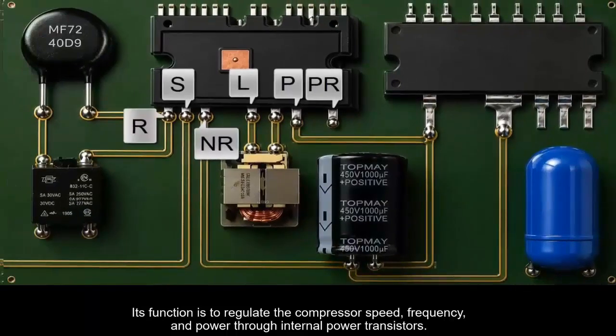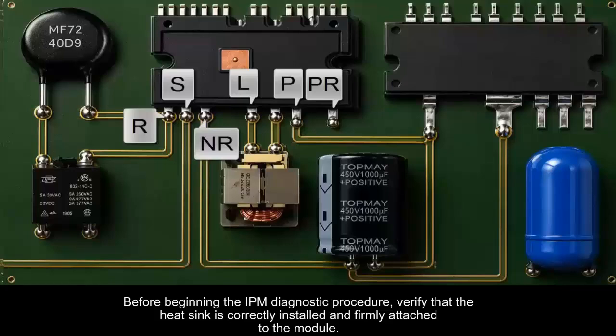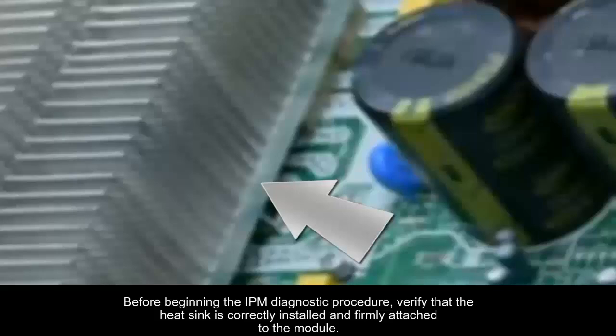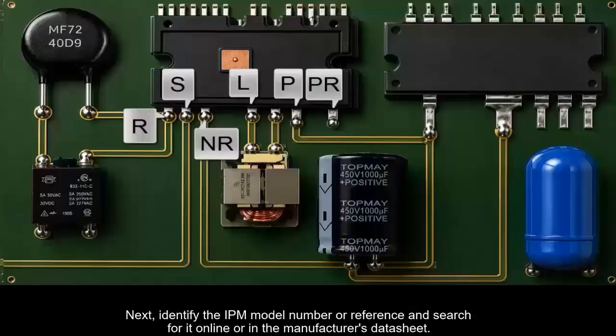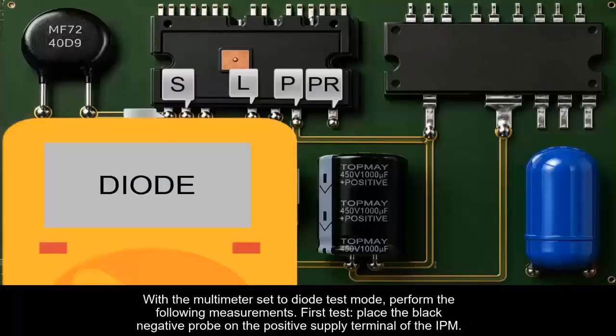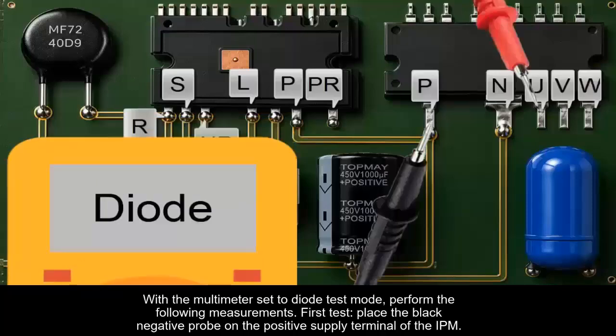Before beginning the IPM diagnostic procedure, verify that the heatsink is correctly installed and firmly attached to the module, since poor heat dissipation can cause overheating and internal damage to the IPM. Next, identify the IPM model number or reference and search for it online or in the manufacturer's datasheet to correctly identify the function of each terminal or pin. With the multimeter set to diode test mode, perform the following measurements.